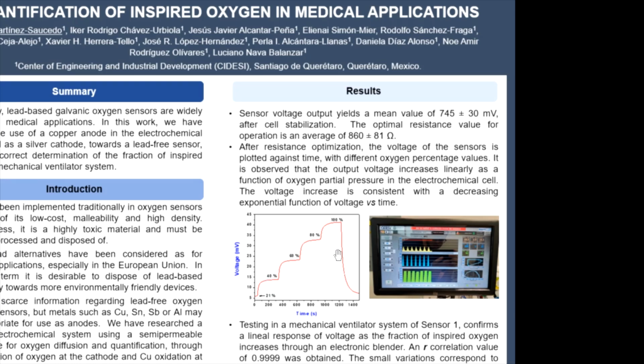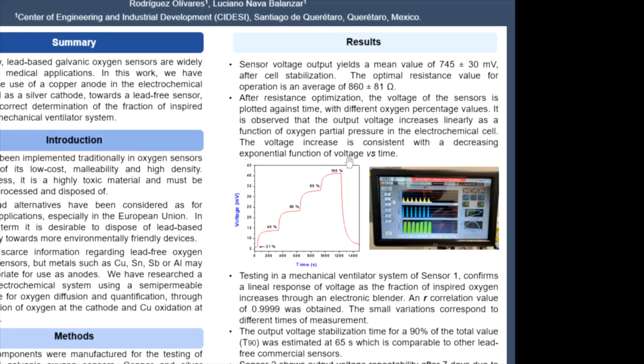You can see that with different oxygen percentage values, the voltage increases, just as described by the Nernst equation. And we can observe that the increase in voltage is linear as a function of the oxygen partial pressure that diffuses through the semi-permeable membranes in the electrochemical cell. Now, the voltage increase is consistent with an exponentially decreasing type function of voltage versus time.